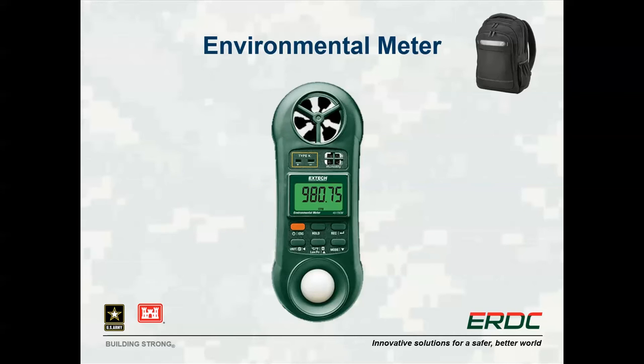The environmental meter, or 4-in-1 meter as it is sometimes called, is a Swiss Army knife of energy auditing. It can be used to measure temperature, humidity, wind speed, and illuminance. Noteworthy examples include measuring lighting levels throughout the building and comparing to ASHRAE recommendations, which may be useful to reduce lighting levels in some hallways or corridors, or taking rough airspeed, temperature, and humidity measurements in an air handling system.